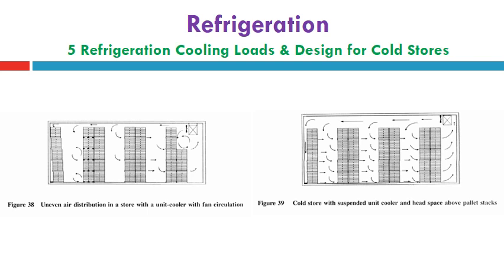As can be seen in this slide, it presents the good arrangement and the bad arrangement of air movement inside. On the left-hand side we can find wrong installation of the pallets, uneven air distribution in a store with a unit cooler with a fan circulation. The air couldn't reach all products at the same time, and some products can be damaged because unrefrigerated air can reach them. However, on the right side, figure 39, we can find fair and even distribution of cold air with a suspended unit cooler, with the required space kept above it.